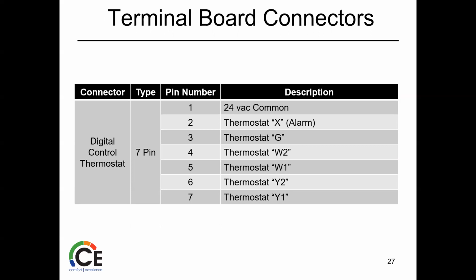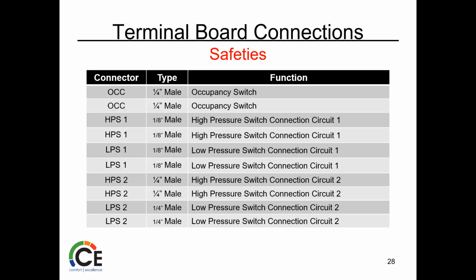Common. I don't usually use X much. That's just if you have an alarm set up, if somebody wants to flash a light, unit's not working or whatever. G, W2, W1, Y2, Y1. And we'll talk about it later, but you notice there's no O here. So we don't worry about reversing valve control.